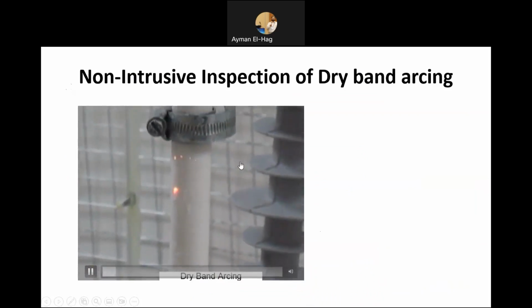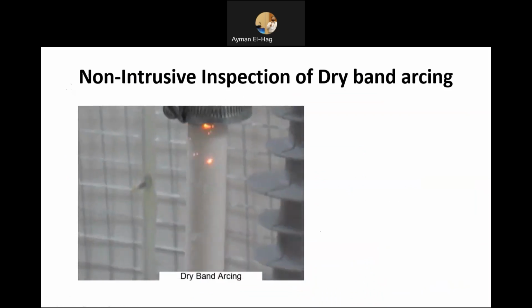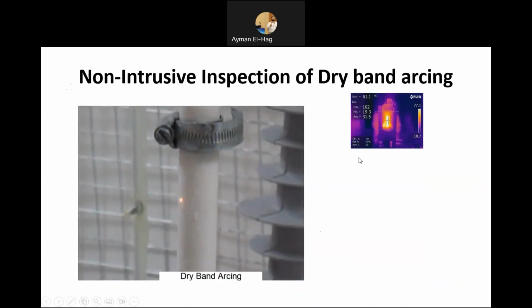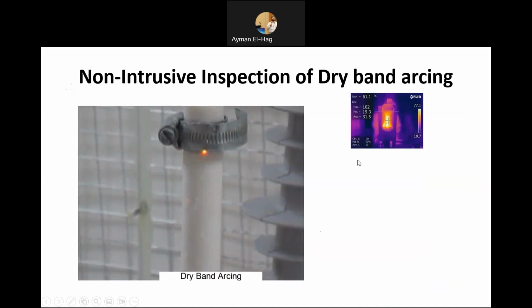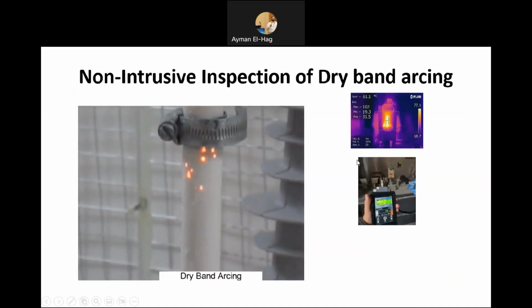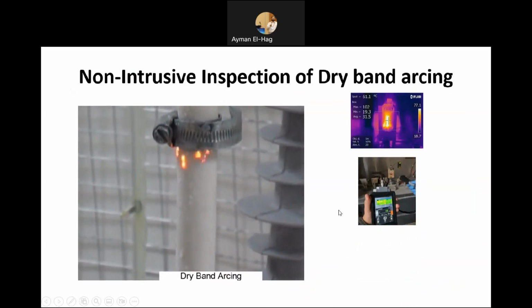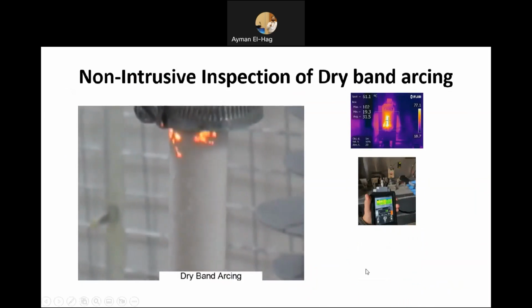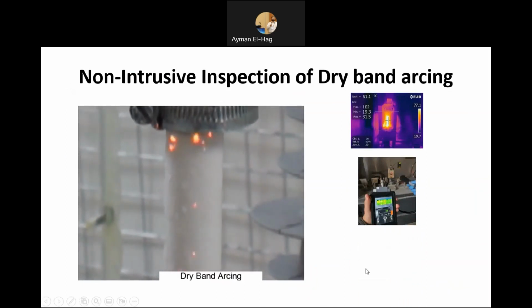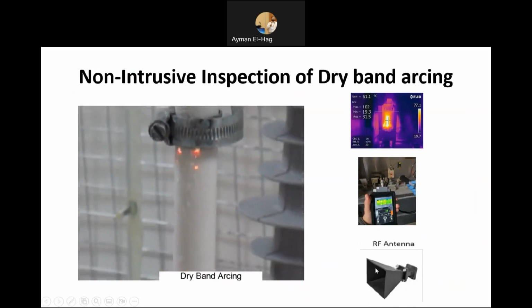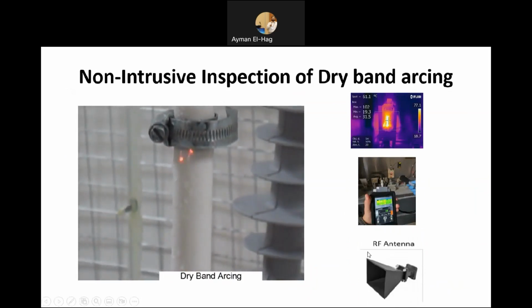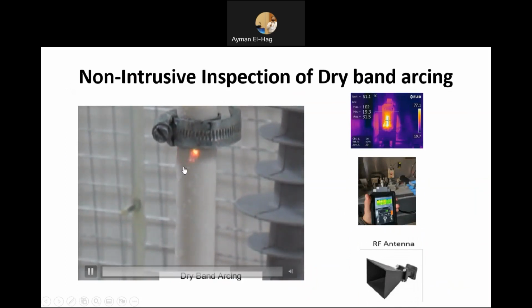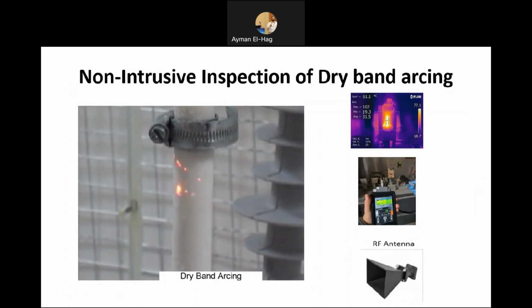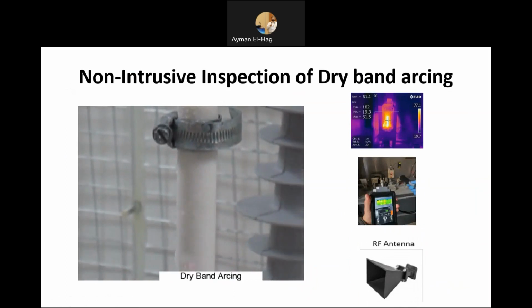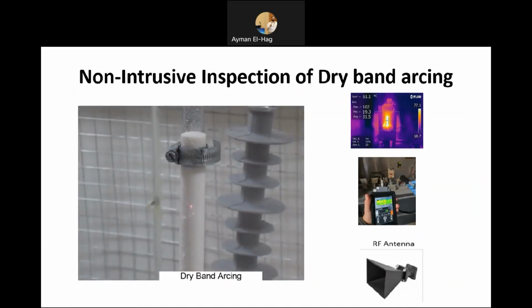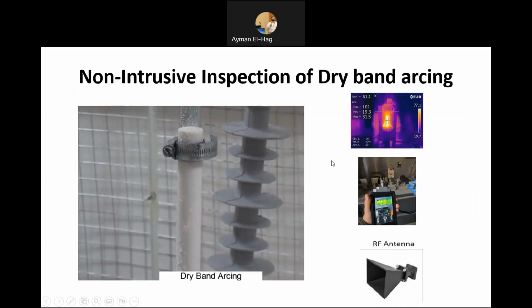So now, whenever there is dry band arcing, there is heat, so you can use the IR camera. There is sound coming from the dry band arcing, so you can use an ultrasonic sensor. And there is a radiation of electromagnetic waves, both low and high frequency. The high frequency can be detected by the RF antenna. So this physical fault, dry band arcing, that can lead to complete failure of the insulators, can be inspected using these three methods.